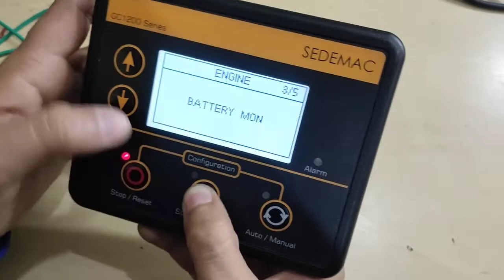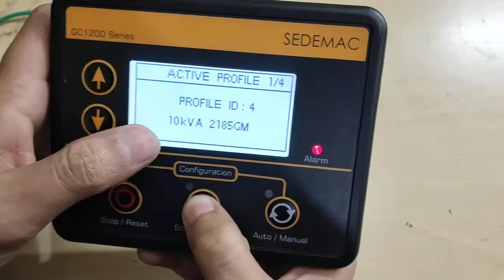And maintenance, governor: you can configure your governor here. This controller supports a governor, so you can select your governor here, with actuator speed and direction, anti-clockwise or clockwise. You can see and change the ID active profile. If you want to change the profile you have selected earlier, you can do it here by pressing the start button and going up with the up key. Usually these controllers support genset ratings from 5 kVA to 82.5 kVA. So here we can come out of it now, and this is all.